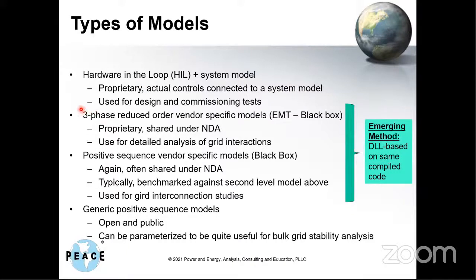The next layer of modeling is three-phase models in EMT tools, electromagnetic transient tools, like EMTP, ATP, or PSCAD. Again, these are typically proprietary, but shared with utilities and consultants through non-disclosure agreements. The emerging method is a DLL-based model, created by compiling the actual source code from the hardware, which is then linked into the EMT model.